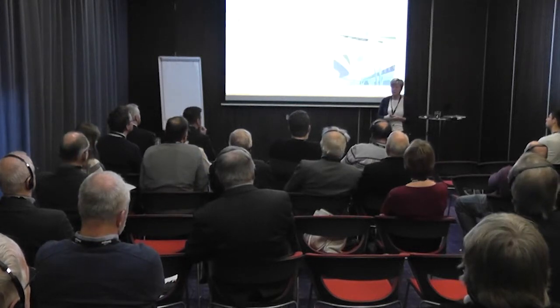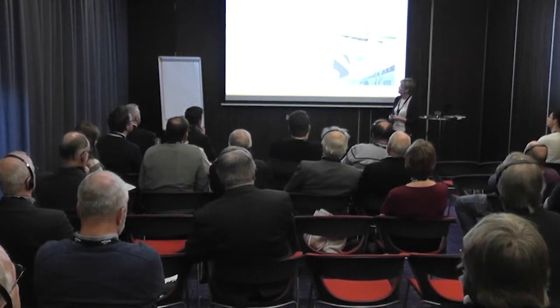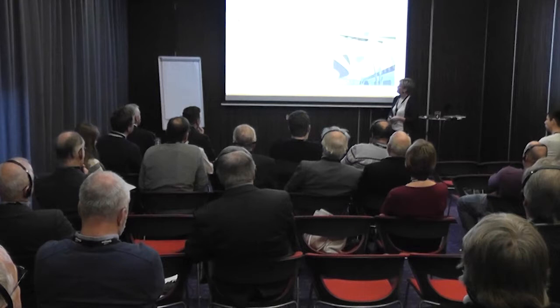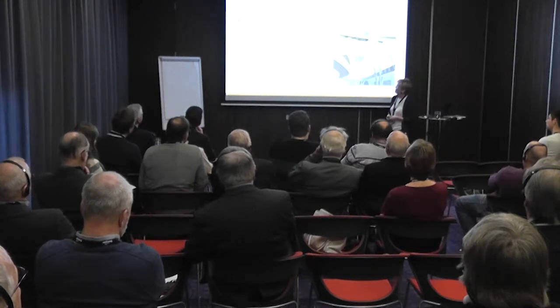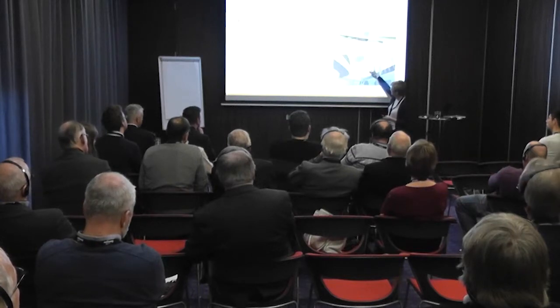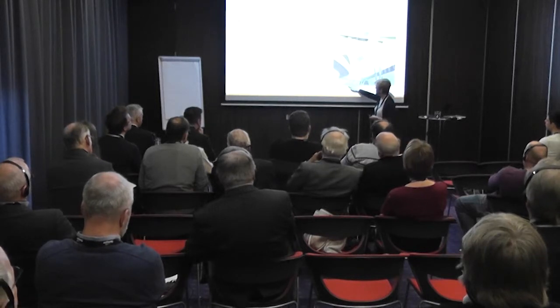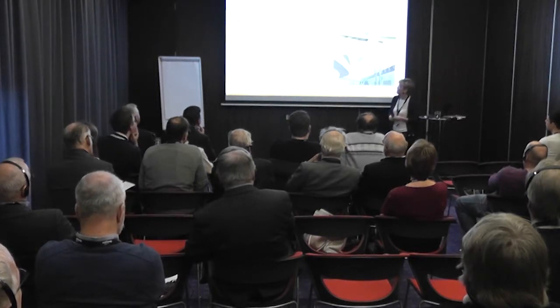So this leads us to the winter situation. The windows have a U value of 1.2, so it's not the best. Today we would have chosen better, I'm sure. And here, as I told you, we have these spoilers or shelves up under the windows, and we have floor heating, and there's a few radiators along the facade at the south side, but nothing up in these big facades.